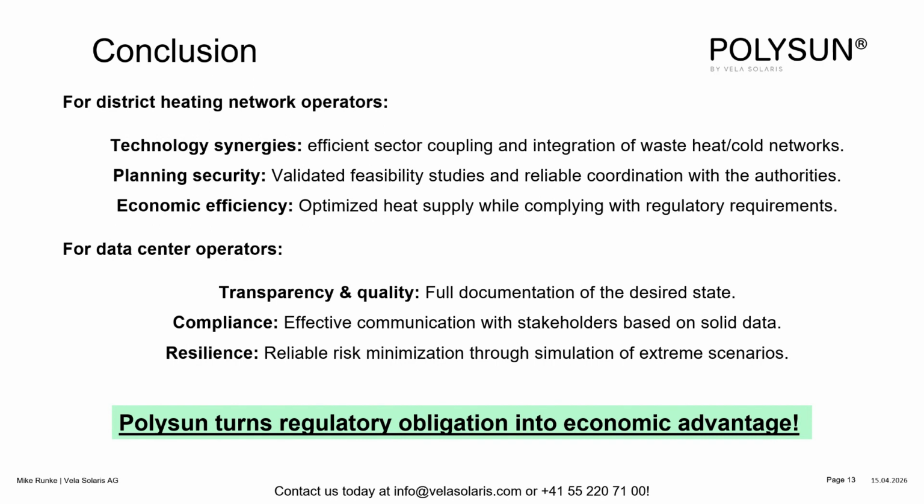However, the system logics of the data center and the heat network can conflict. The heat network requires low supply temperatures, high utilization, and cost-effective heat generation. The data center wants stable IT temperatures for the servers and as few external interventions in its cooling systems as possible.